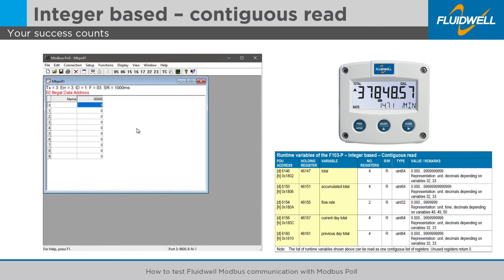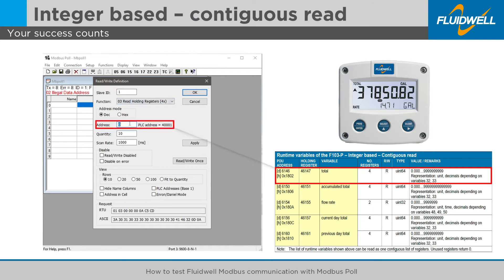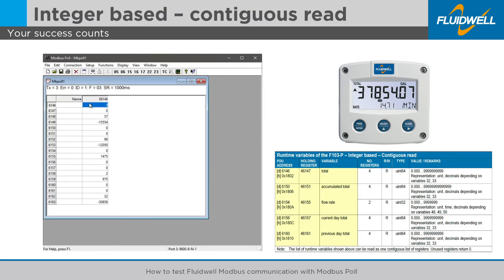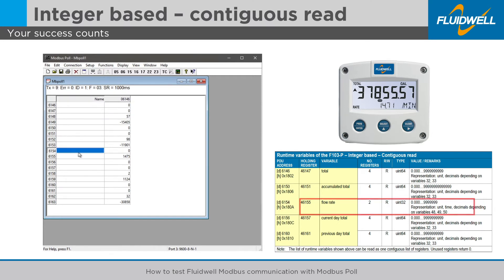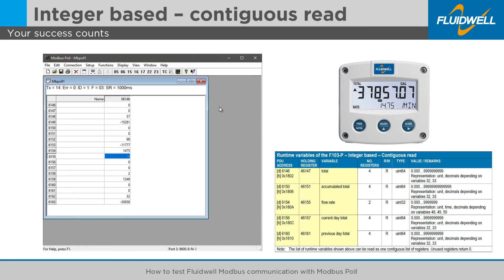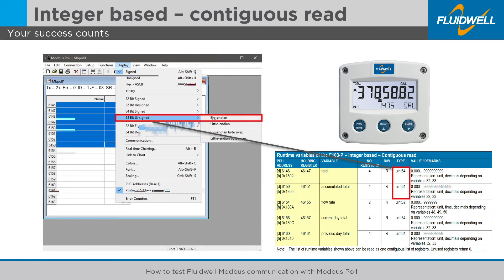For an integer-based contiguous read of the total accumulated total, flow rate and daily totals, select the corresponding table in the manual. The table shows the first PDU address of 6146 and the total number of registers of all variables is 18. For the flow rate data, apply the 32-bit unsigned integer data type. For the rest of the variables, apply the 64-bit unsigned integer data type. Always select Big Endian register order for a correct reading.